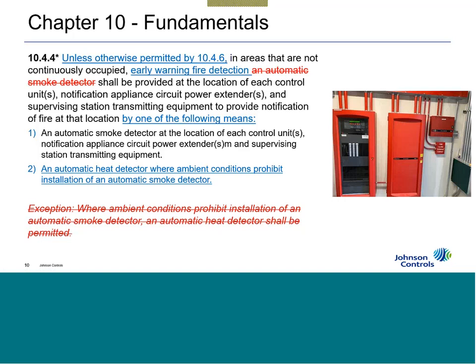What NFPA has done to change their manual of style is they're telling the committees where you can stop using exceptions. The code should be able to be standalone. I shouldn't have an exception that's possibly open to interpretation. So here, the code has said you need to have a smoke detector at each of these devices, or if the ambient condition prohibits it, a heat detector. Now, you can argue that, well, gee, if the ambient condition doesn't allow a smoke detector to be there, is it really a good place for a control unit? And that's another discussion. But if we find ourselves in those situations, the code allows us. So they've got rid of the exceptions and put a smoke detector above your control units.